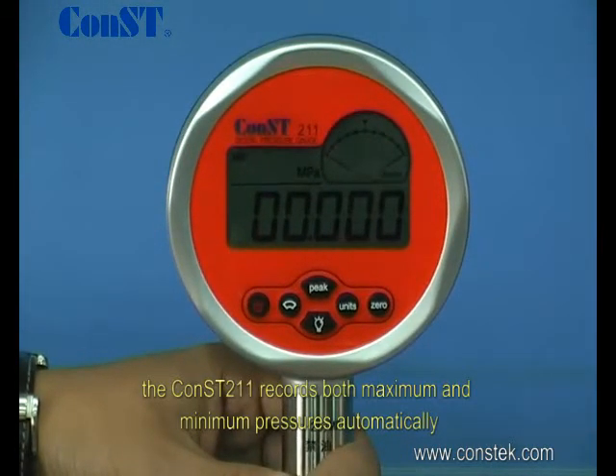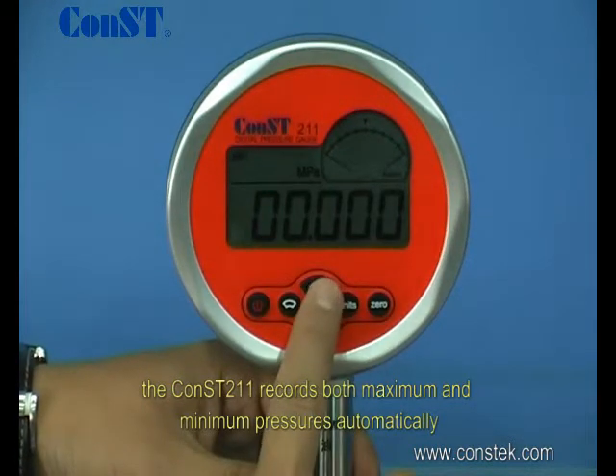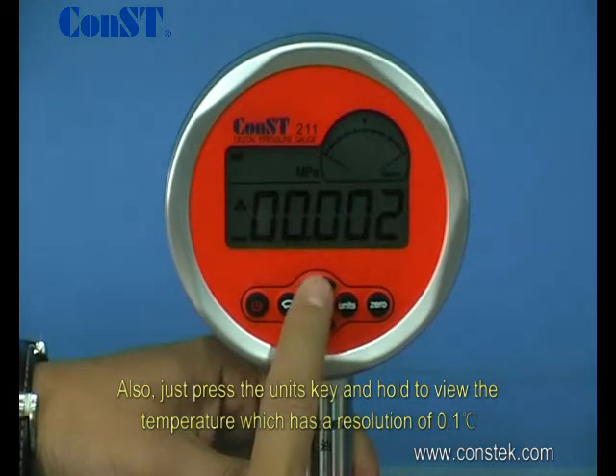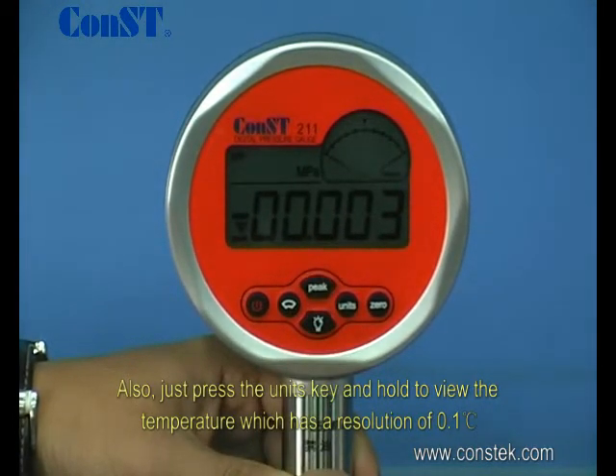Along with its calibration functions, the ConST211 records both maximum and minimum pressures automatically. Just press the units key and hold to view the temperature, which has a resolution of 0.1 degrees Celsius.